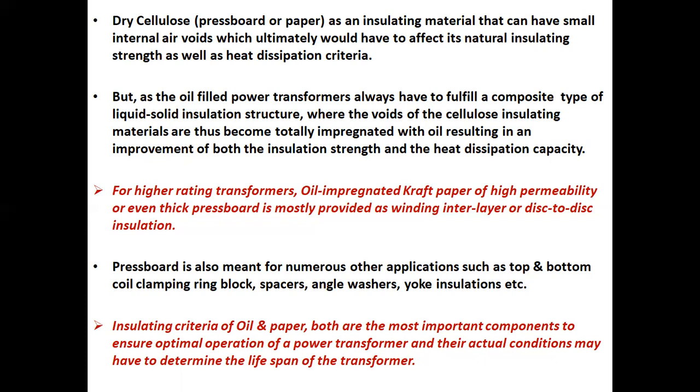For high rating transformers, oil impregnated kraft paper of high permeability or even thick pressboard is mostly provided as winding interlayer or disc to disc insulation.